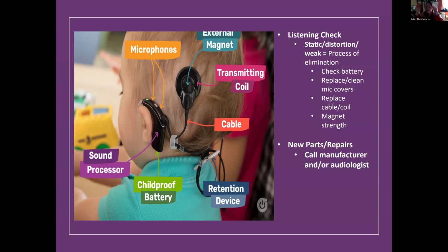You kind of have to just do a process of elimination at that point. Another part you want to check too is the external magnet. So how is it attaching to the skin? Is it coming off really easy? Like, have you noticed that the kiddo runs to the other side of the room and then it falls off? It could be that that magnet is no longer the best strength for the kiddo, and maybe they need a little extra strength, or maybe vice versa. Maybe it's too strong a magnet, and you need to go down a little bit there.